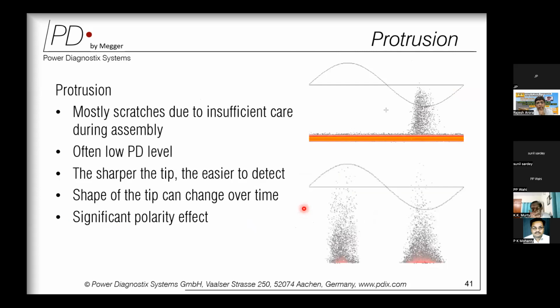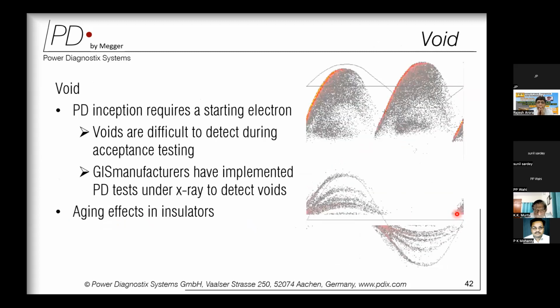These are some more examples of PRPD patterns you can see when you have a protrusion. Whenever it's a protrusion, the effect is seen more towards the peak of the positive or negative cycle, because during that time the PD levels are higher. If it is a void, the pattern could be similar to this, which is dense at the edges and less dense inside the envelope. This is the typical pattern of a void.